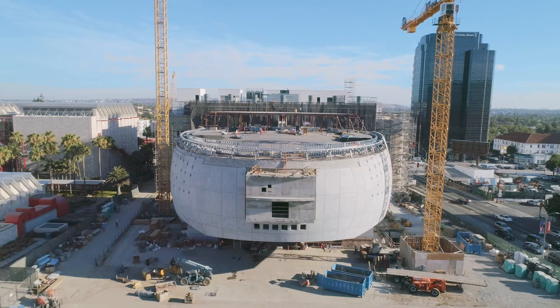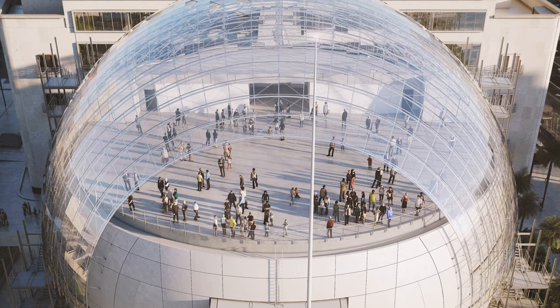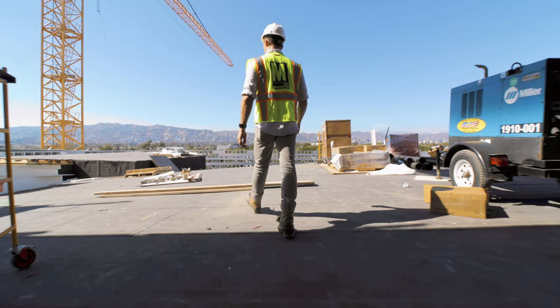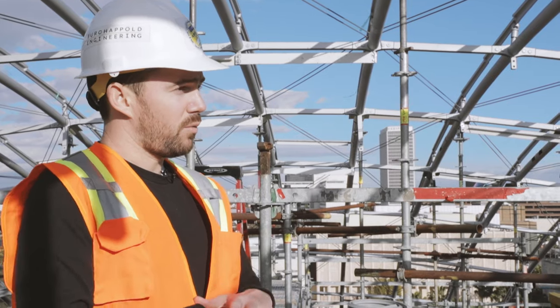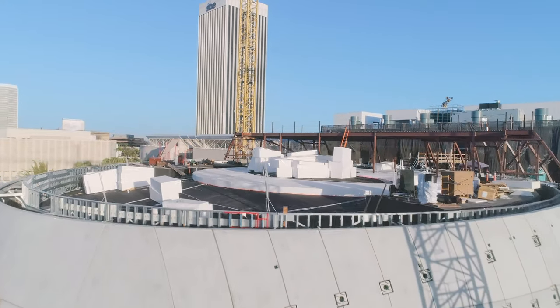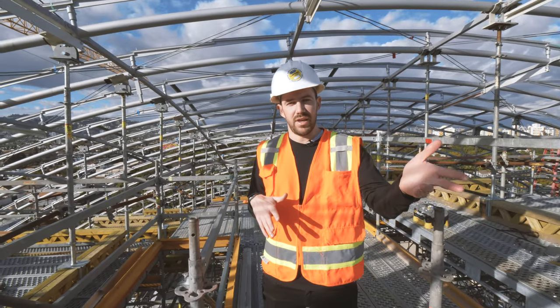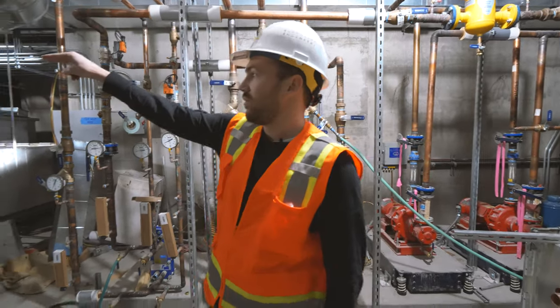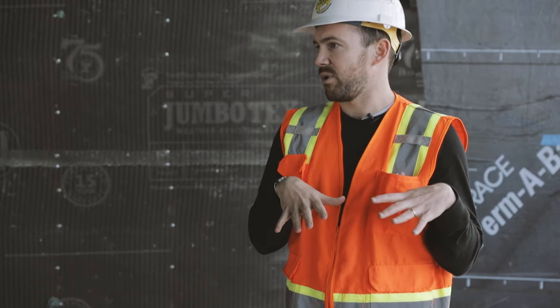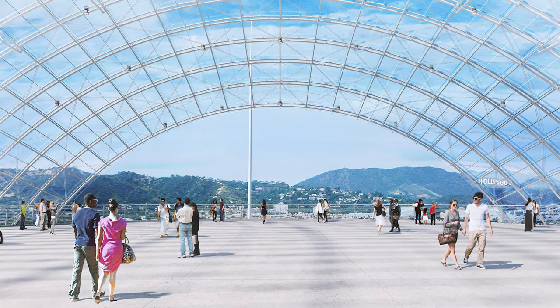This is the Dolby Deck — a large outdoor terrace covered with a glass dome. The entire terrace is exposed to the elements, so the dilemma as an engineer who wants to be sustainable is how do you condition an outdoor space without just wasting energy. The terrace below is one large radiant floor slab which can be used in heating or cooling. We're capturing the rejected heat from the heat recovery chiller in the other building and using it over in the radiant floor, so in an evening event where you've got people outside wanting to keep warm, we're pushing that heat into the radiant floor slab and providing some level of conditioning.